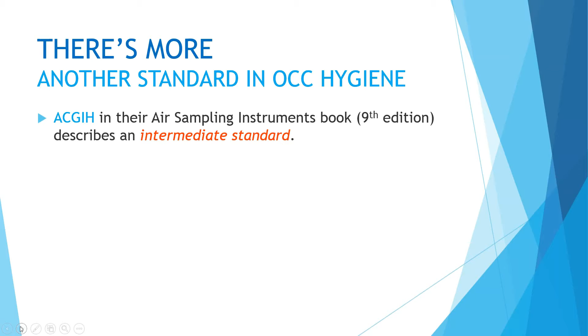An intermediate standard is a highly accurate secondary standard that provides an accuracy nearly comparable to that of a primary standard, but which of themselves cannot be calibrated by internal volume measurements. And it goes on to say that intermediate standards provide an accuracy of approximately 1%. So I was happy with this definition because I finally got a stated accuracy assigned to a particular type of standard. Again, 1%. Sorry.